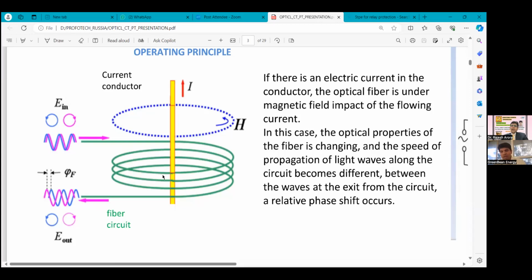So the main thing is, tell me how do you differentiate between the different metering classes 0.1, 0.2, 0.5, 1? According to, sir, the thing is that the class, what I can understand is everything is done at the EPU only. The basic principle of it will be measurement done because this spun fiber only measures the current, and according to the measured current, the light source will be fed to the EP unit. So based on light frequency, it will check. It will sense the light frequency, and accordingly it will give the result.